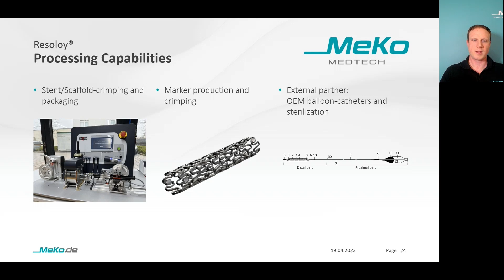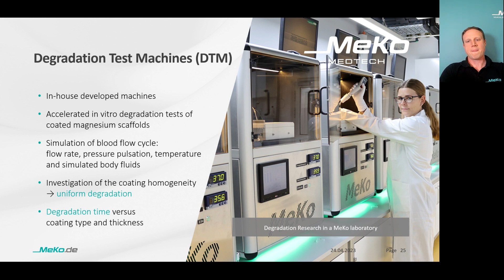To test the degradation kinetics of magnesium-based scaffolds, MeKo developed its own degradation test machines. These are comparative tests in pulsatile simulated body fluids to investigate degradation homogeneity depending on coating type and thickness. Here you will see the principal setup of the degradation test machine. A peristaltic pump pumps the SBF, the simulated body fluid, through the mock vessel where a stent or scaffold is placed. The ambient air and the SBF are heated to 36 to 37 degrees Celsius, and the flow is measured.